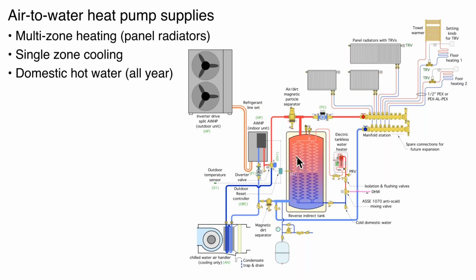So this tank can be maintained at some elevated temperature in the summer to either preheat or fully heat domestic hot water. And your control system, and some heat pumps today actually have these controls built in, can determine which is the priority load. If you have a simultaneous call for cooling and domestic water heating, one of them has to take priority. And often it's just a dip switch or a software setting that allows you to pick which one you want. This tank has internal coils. It's a reverse indirect, so basically cold domestic water comes in, goes up through the tank, which is maintained at temperature, and it might be 110, 120 degrees. So you could get a substantial, perhaps even all, of the temperature lift required for domestic hot water.